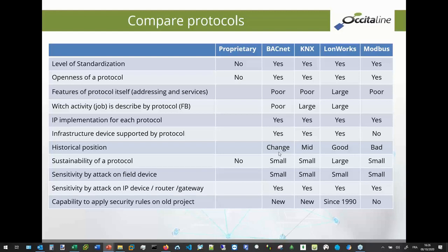The historical position. We will see in just a couple of seconds after this slide. The position in history is very, very good for LON because it has never changed, or it's completely compatible with the old version. KNX is often the same, minus the security, because the security was implemented a couple of years ago. And BACnet changes every 3 months. Today we have a new revision of the documentation. It's BACnet 2020. I just downloaded the new BACnet Bible this morning, but it's just crazy.